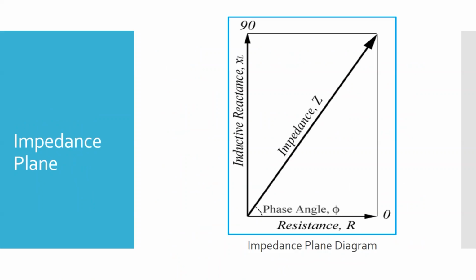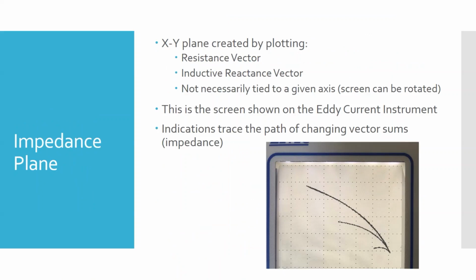When we're doing corrosion, we kind of put it in the center of the screen, which makes a little bow tie or flower-looking symbol. Keep in mind that even though this says resistance here for the phase, we can take this whole view and rotate it any direction we want. I mentioned that resistance tends to be fixed while inductive reactance will change - if that was the case, it would always just move up and down along this line, but we can rotate this any direction we want. That's one of the things you'll note in your report, the phase angle, which is the rotation of the screen.